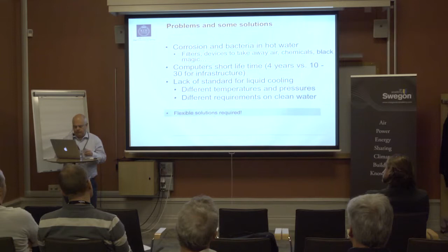We've been talking about capturing the heat close to the source. The best way to do that is direct liquid cooling, like in this image where you see the CPUs and the copper tubes going out to the heat sources. If you don't do that, it's probably better to encapsulate the heat in some way to take it as close as possible to the source, as we've discussed before.